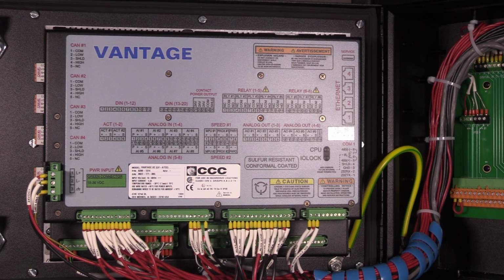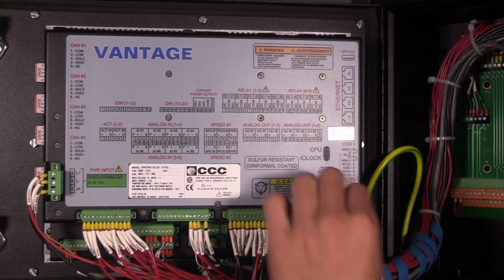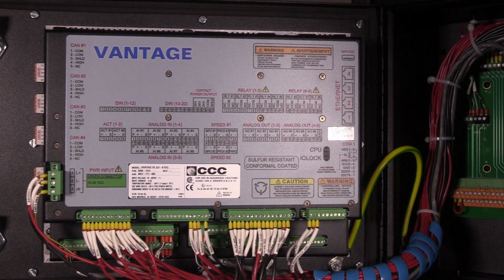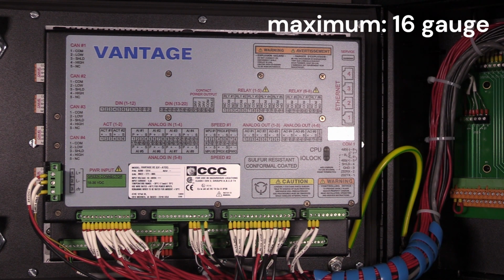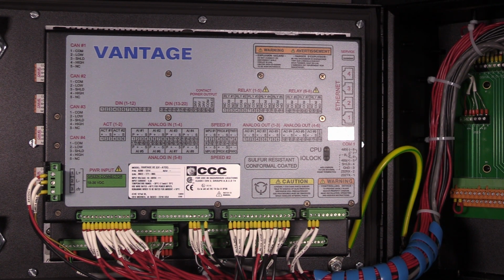All wiring in this section will be wired to the terminal blocks of the controller. You should remove the terminal blocks from the controller before connecting wires to them. The terminal blocks will accept a maximum wire size of 16 gauge. Each wire should have a 1/4 inch of insulation removed to create a connection without exposing too much wire. Please note that the order to which you connect the wires does not matter.